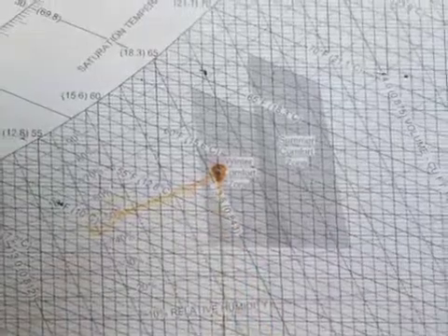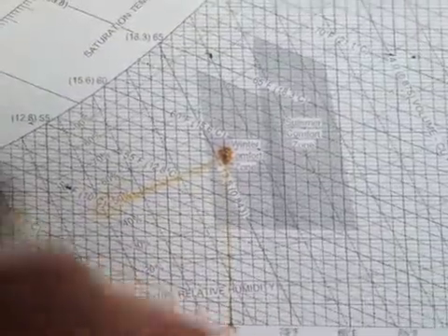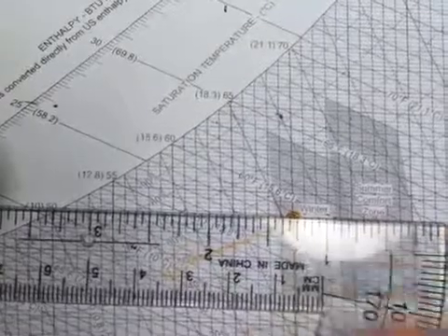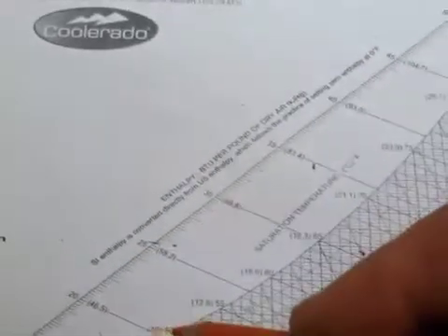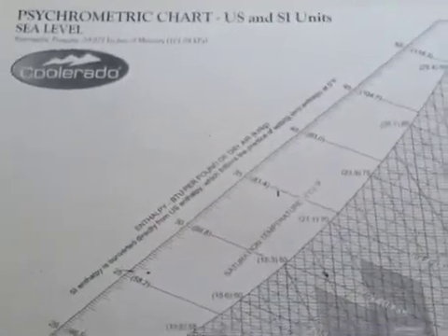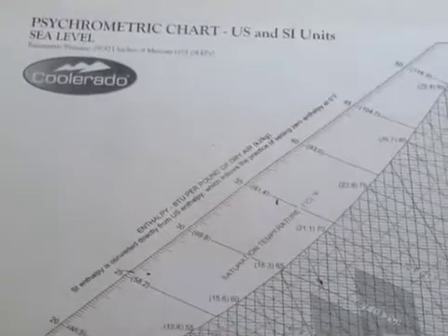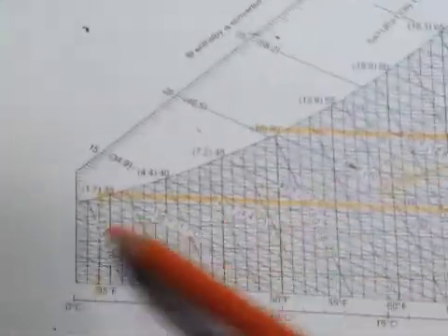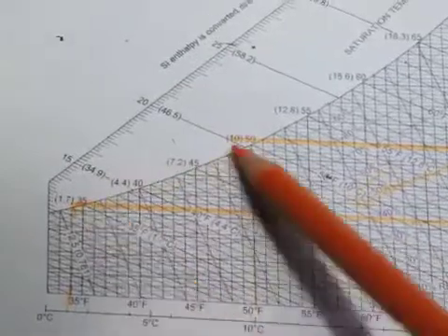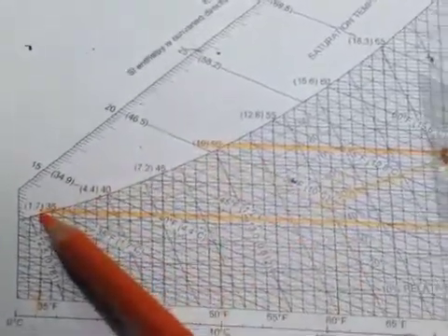And we want to find out when that amount of moisture in the air is cooled off to 33 degrees Fahrenheit, which is over here, how much of the moisture is likely to condense out. Well, we can find that out by drawing a straight line to the saturation curve on the psychrometric chart. Now, that obviously is condensing at 50 degrees Fahrenheit, and we have a 33 degree Fahrenheit. So we have the potential for condensation between 50 degrees and 33 degrees.